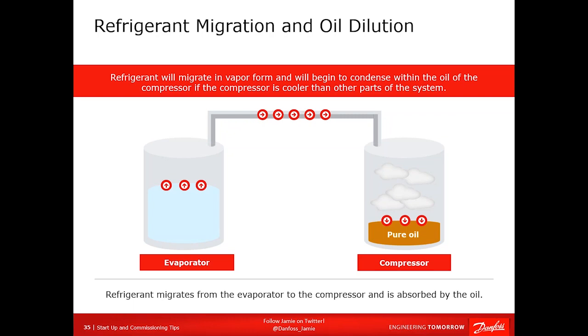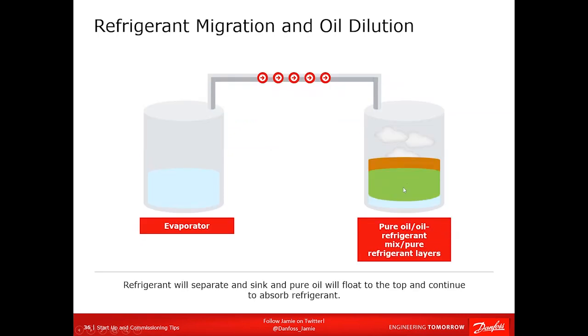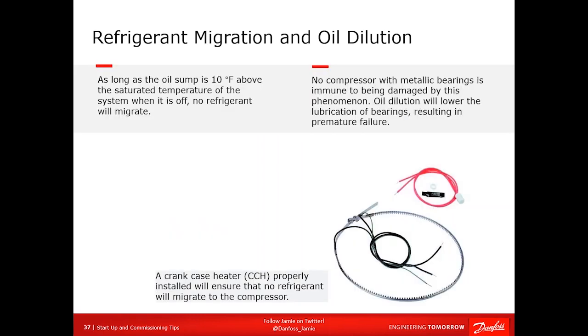So, off-cycle migration. This is essentially where you have the compressor sump with the oil in it colder than the rest of the system, which means its vapor pressure is lower. So what happens? Well, the refrigerant vapor migrates to the oil and the POE oil absorbs it. And when it does that, the liquid refrigerant drops to the bottom. You've got pristine oil at the top. It continues to suck in the refrigerant until it tries to start the compressor. The sump pressure drops. This instantly becomes foam, and you either lose your pump pressure or you dry clean your bearings free of oil. Either way, it's bad news.